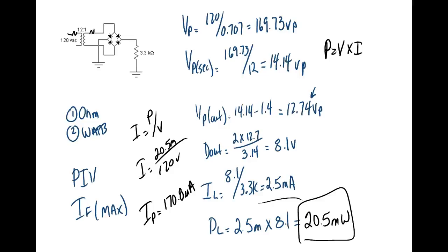So the transformers that we have are 12.6 volts, 1 amp. So 12.6 volts, 1 amp, so that'd be 12.6 watts that transformer is designed to handle, right? A lot of your small commercial transformers are rated in volts and amps on the secondary side, because they're designed to go on standard 120 volts on the primary. Most of your commercial transformers have 120 volts on the primary, and then they'll give you the voltage on secondary. And if they give you the secondary current and the secondary voltage, you can multiply those two together and get the wattage required by the transformer, right? Are we okay?